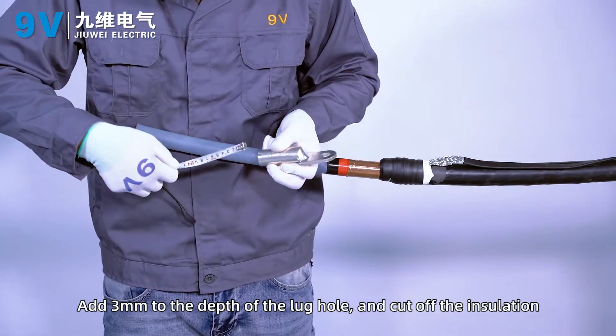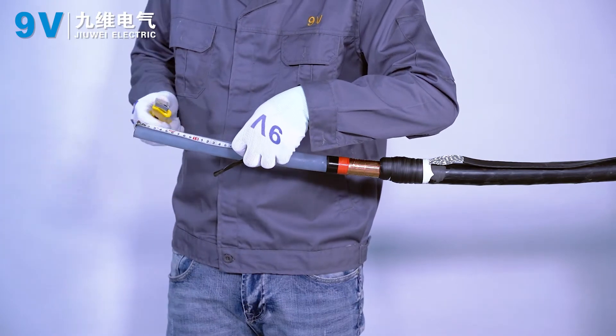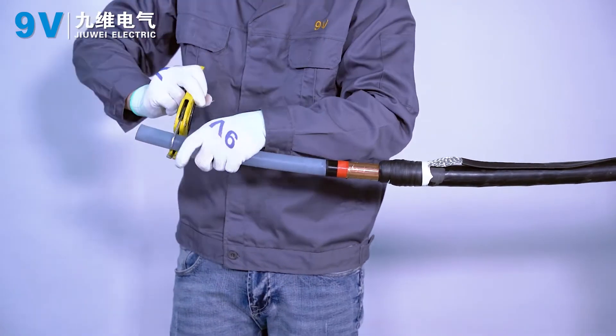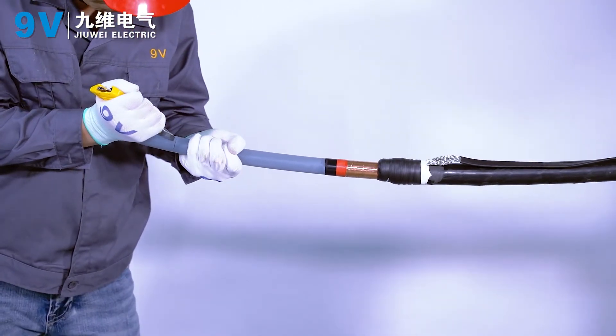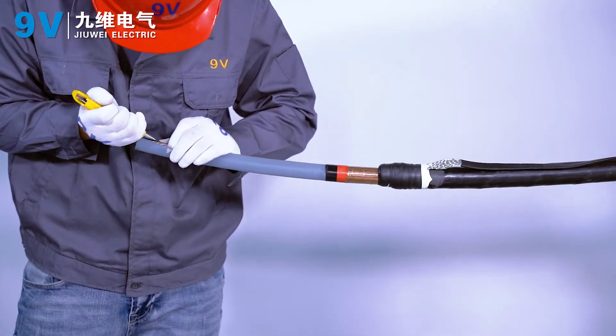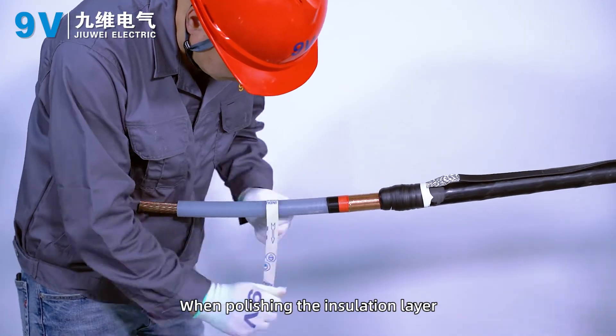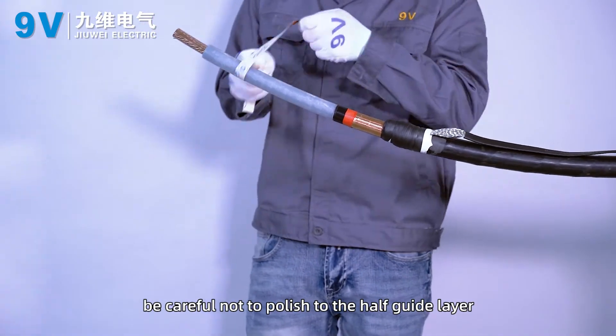Add 3 mm to the depth of the lug hole and cut off the insulation. Sand the surface of the insulation layer with fine sandpaper, being careful not to sand into the semi-conductive layer.